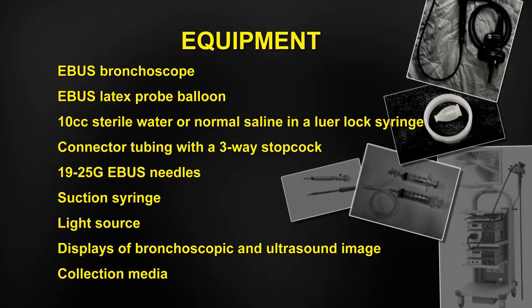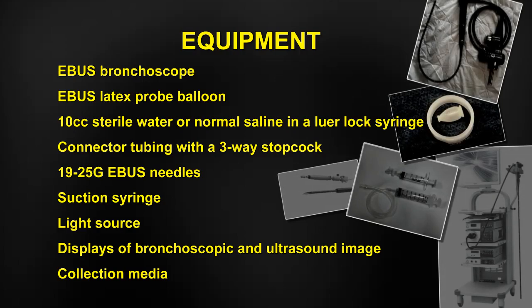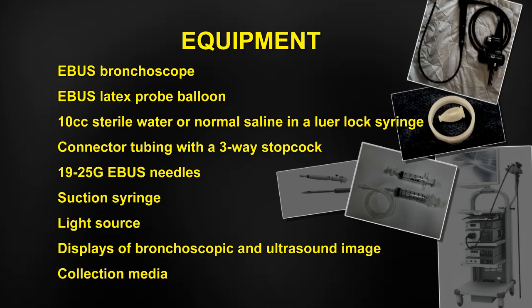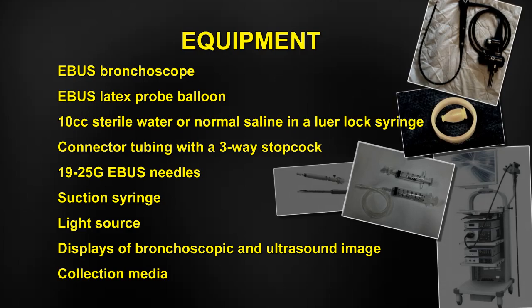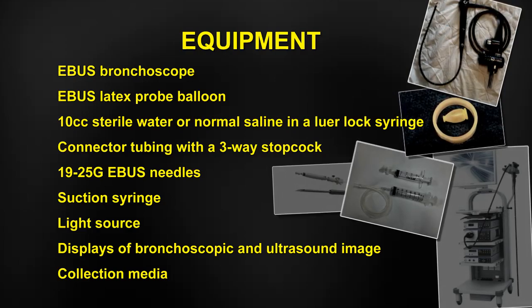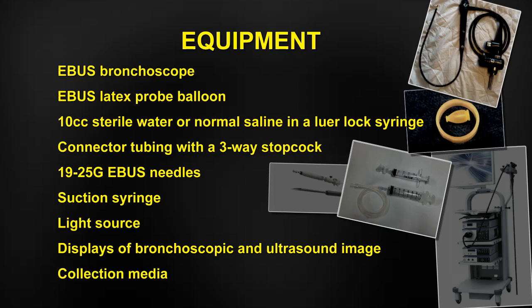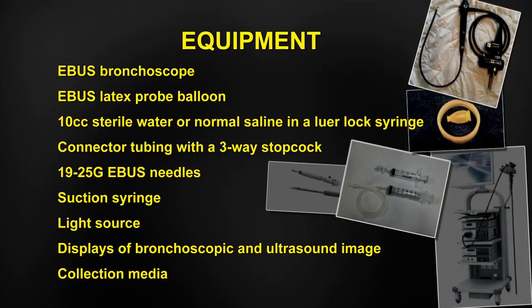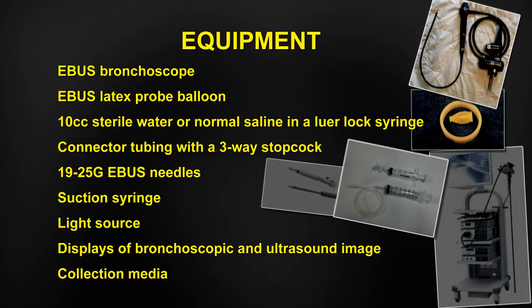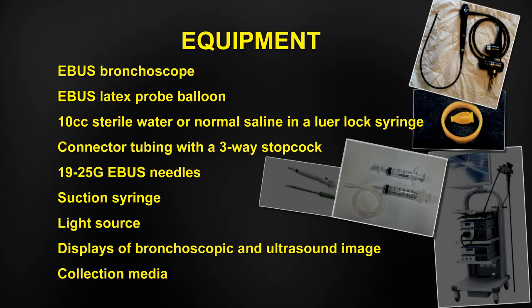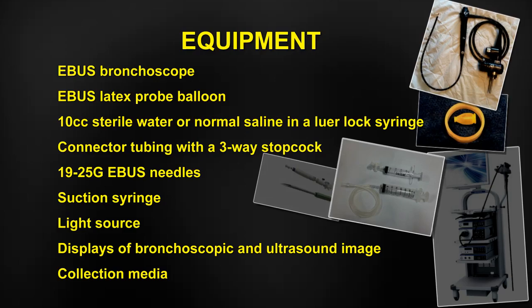Required equipment for endobronchial ultrasound includes the EBUS bronchoscope, of which there are currently three available manufacturers: Olympus, Pentax, and Fujifilm. The degree of view ranges from 10 to 45 degrees depending on the model. Other required equipment includes the EBUS latex probe balloon, 10 cc's of sterile water or normal saline in a luer-lock syringe, connector tubing with a three-way stopcock, tools for biopsy including 19 through 25 gauge EBUS needles and a suction syringe, the EBUS processor with light source and display, and collection media such as Cytorich or RPMI for sample processing.